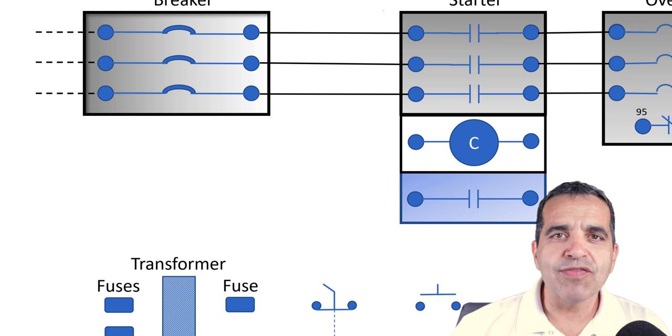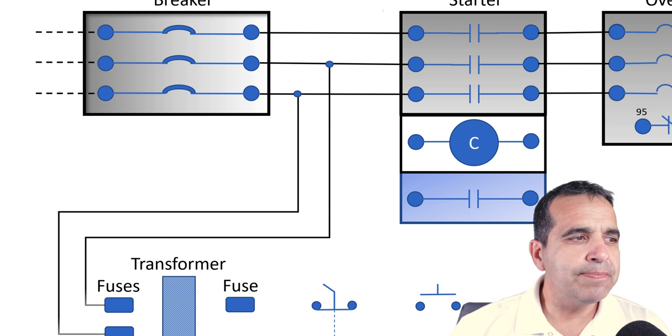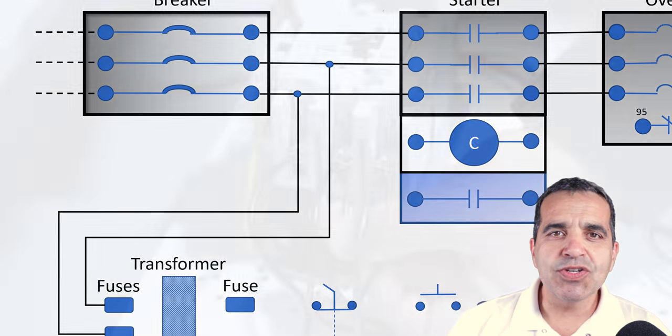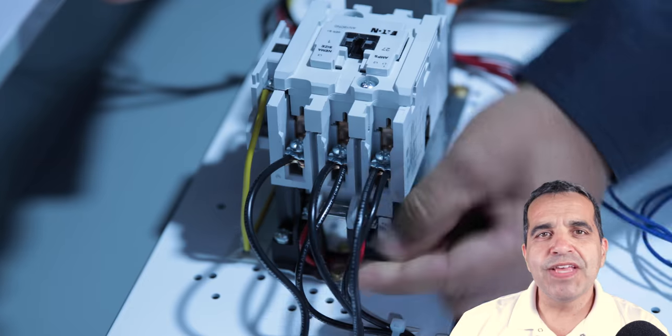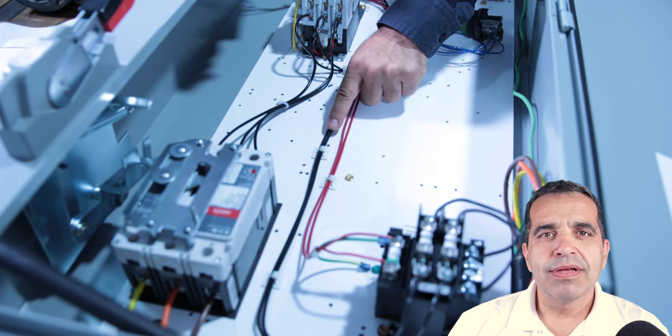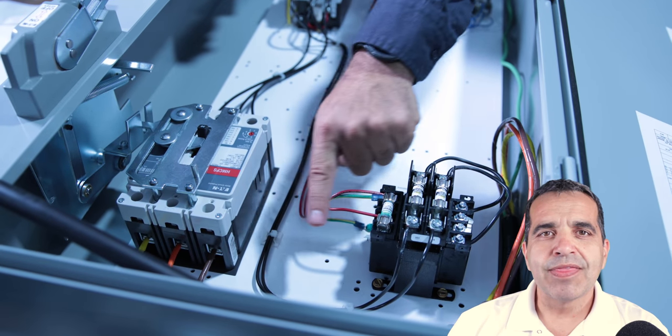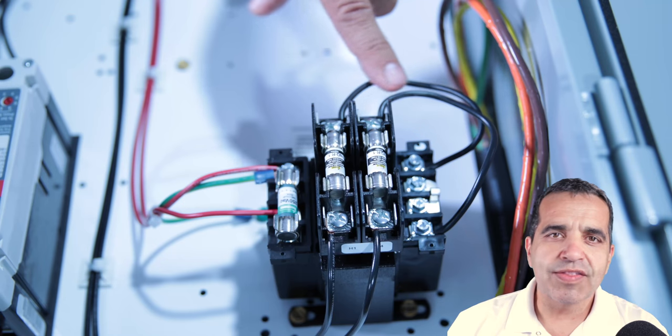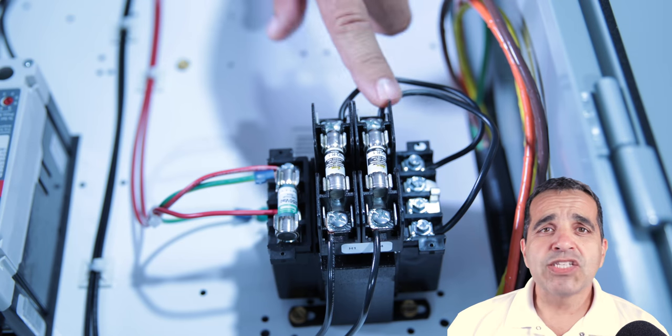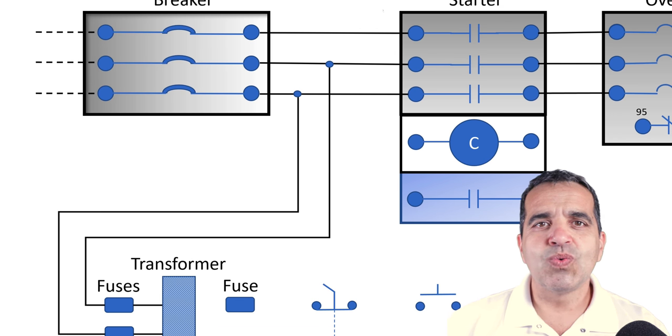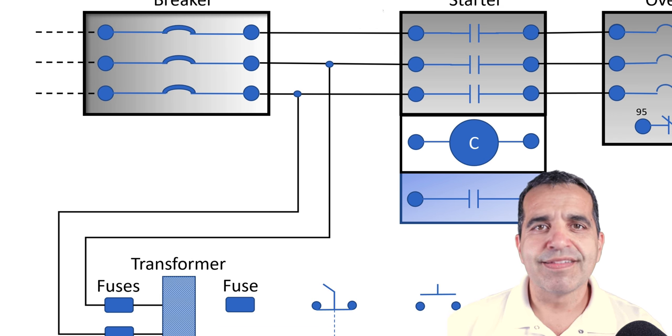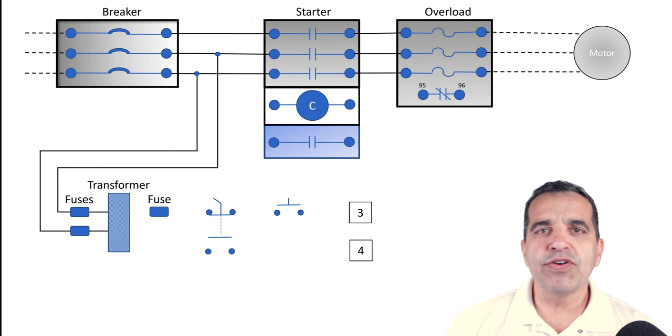I'll show that here on our diagram. You'll see the tap on line one and line two coming down and feeding our fuses, and then those fuses feed our transformer. That transformer is converting 480 volts single-phase to 120 volts single-phase, and we're going to use that 120 volts control power.